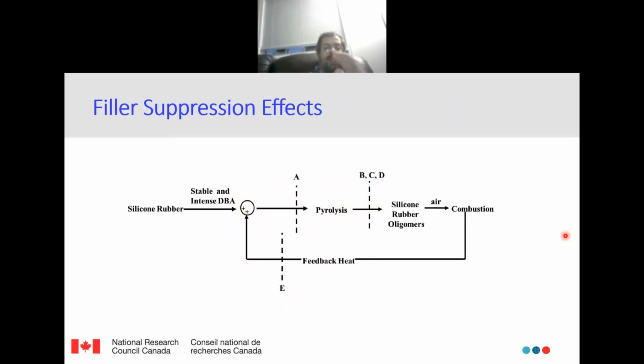I think this is my final slide. So this is what we have. This is a sort of flow diagram of what is happening on the surface of the material. We have the silicone rubber material. Now you will have the DBA, the dry band arcing, start to take place. You will have a pyrolysis effect on the surface of the material. You will have combustion because you have this dry band arcing under air. Now this will come back, and this cycle will keep going on until the material has completely failed on the surface. Our objective is to develop a material that can withstand this cycle for the prescribed time, which is 7 to 10 years.